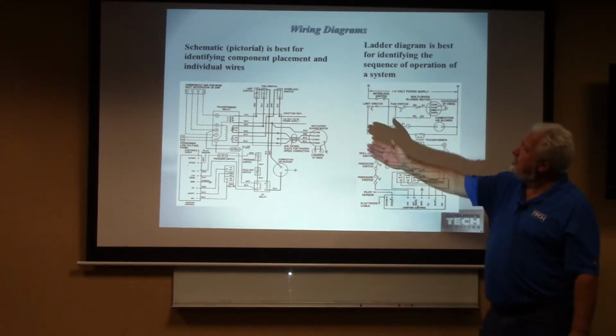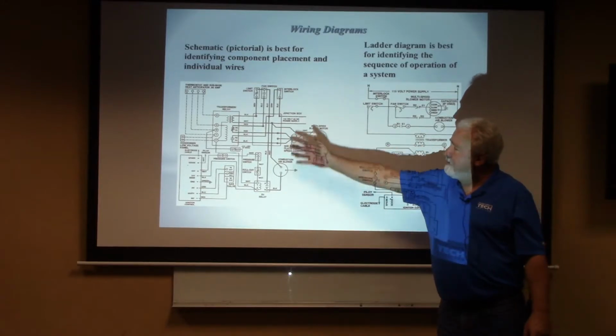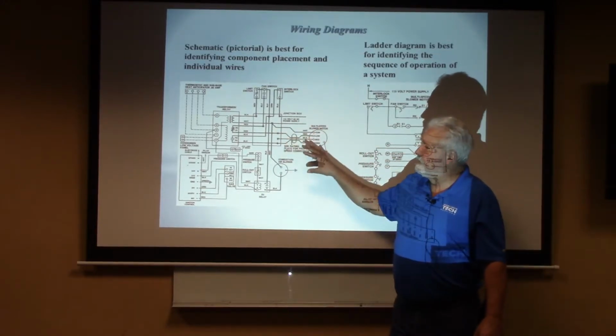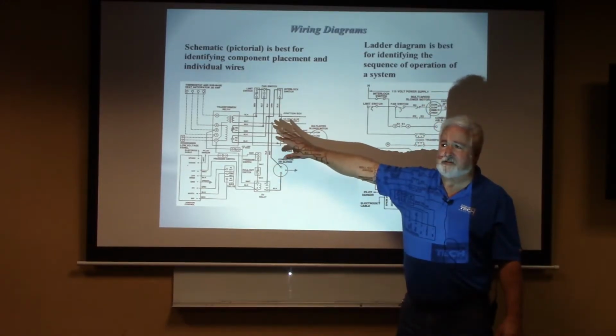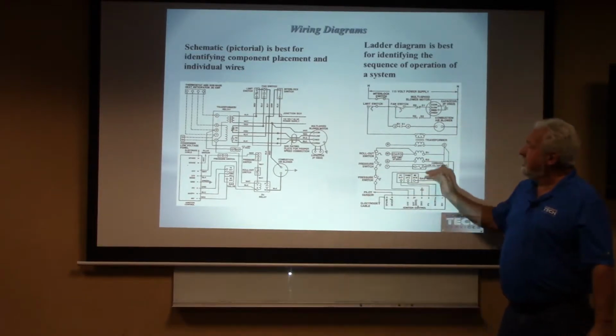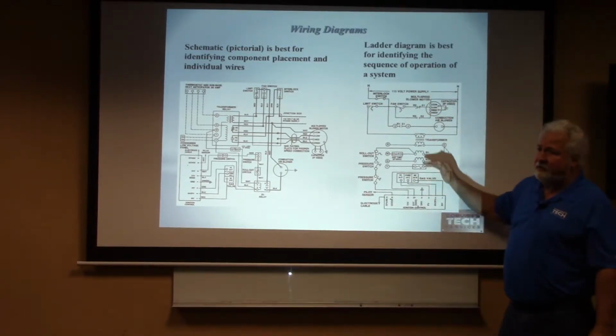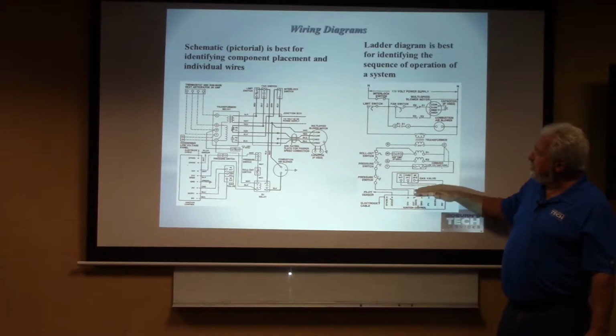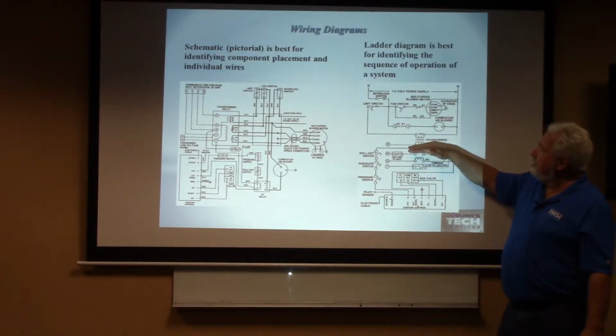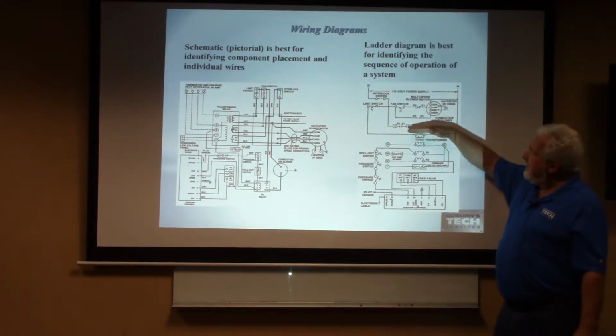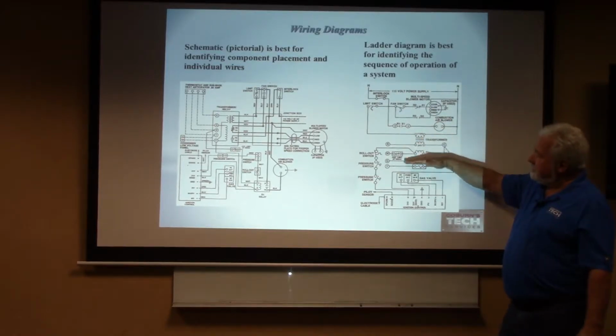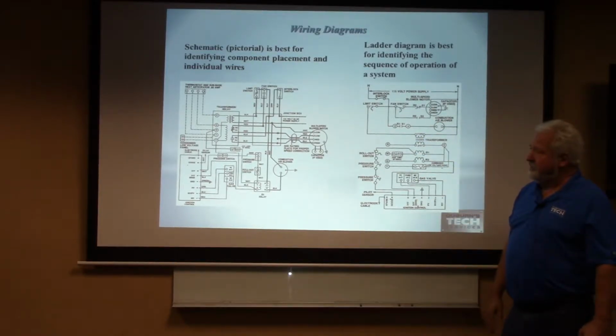Schematics are typically two types of schematics. You can have a pictorial. The pictorial is typically how it's laid out inside the system. And you're going to have ladder diagrams, which is going to be the exact same wiring diagram, but it's going to show you pretty much like rungs of a ladder, everything that's in the high voltage side and everything that's in the low voltage side of that system.